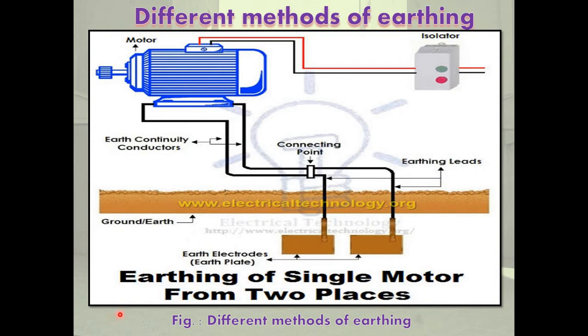Now, these are the different methods of earthing. First example, a motor is connected to the earthing system. These are the motors, these are the isolators, and this is the earth continuity conductor. And these two places are connected to the earthing system. These are the electrodes, earth electrodes.